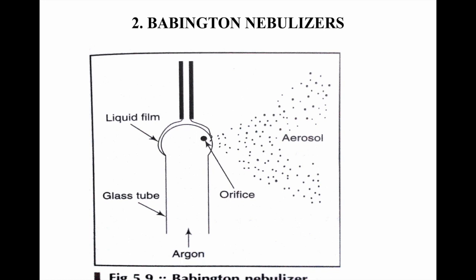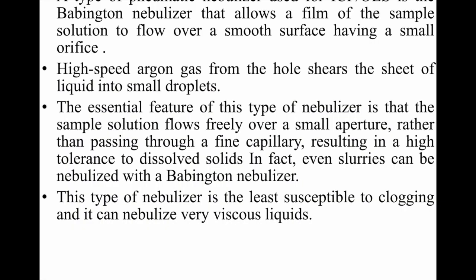The second type of nebulizer is the Babington nebulizer, a type of pneumatic nebulizer used for ICP or OES. It allows a film of the sample solution to flow over a smooth surface having a small orifice. High-speed argon gas from the hole shears the sheet of liquid into small droplets. The sample solution flows freely over a small aperture rather than through a fine capillary, resulting in high tolerance to dissolved solids. Even slurries can be nebulized with a Babington nebulizer. This type is the least susceptible to clogging and can nebulize very viscous liquids.